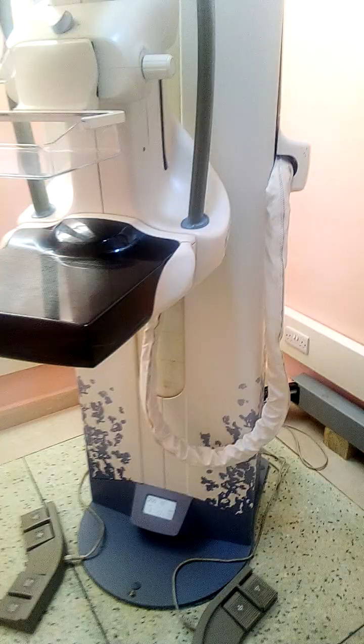Now down here, as you can see, we have a chiller. This chiller is responsible for cooling the gantry, because at times, because of overheat due to use for a long time, or even generation of high rays, the coils for that tube may overheat, so we need to cool it down by the chiller, which has, of course, water inside that pumps this water to the gantry to cool the coils which are inside here.